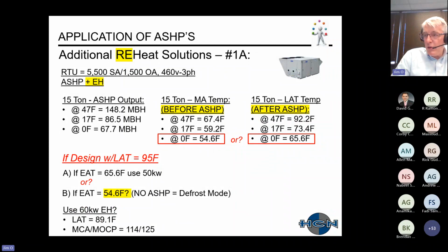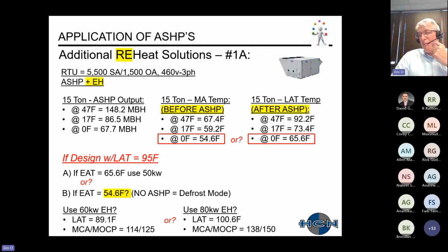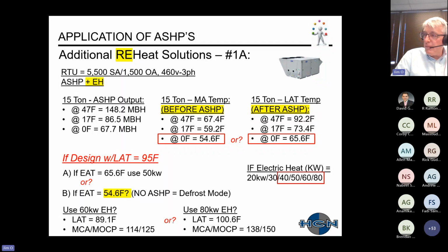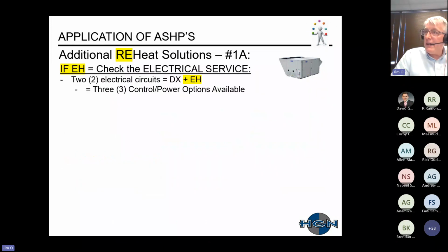If I looked at a 60 kW electric heater, this was my leaving air temperature. And then if I looked at an 80 kW electric heater, that was my leaving air temperature. So those are your associated electrical service requirements. Just want to point out that when you have a unit with electric heaters, depending on your tonnage, you have options for different sizes. They're usually in about 10 or 20 kW increments. So for this unit, we'd be looking at an electric heater approximately in that size.